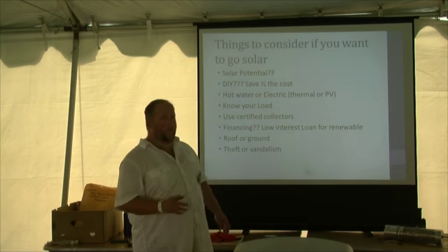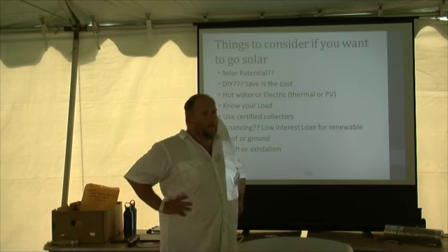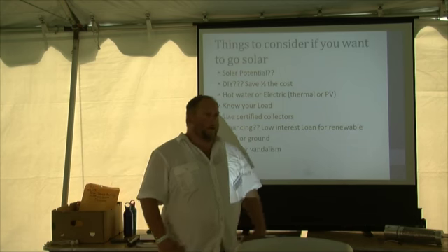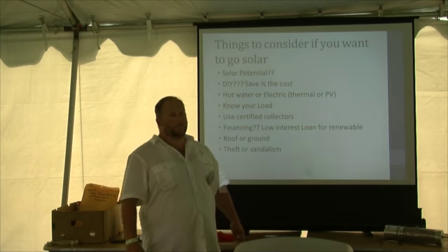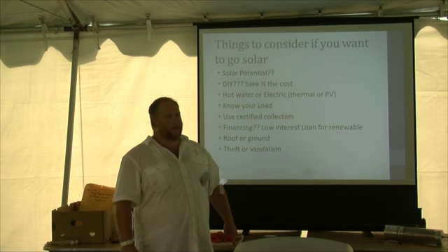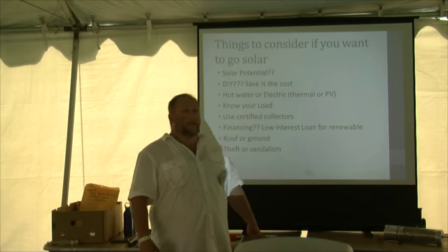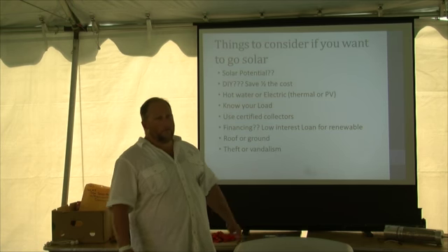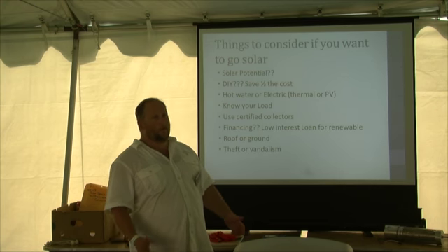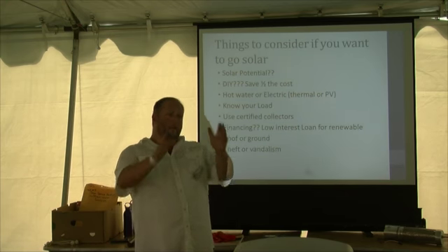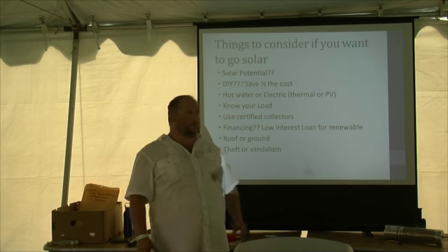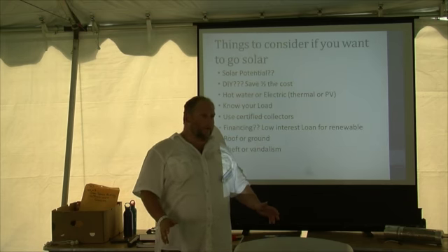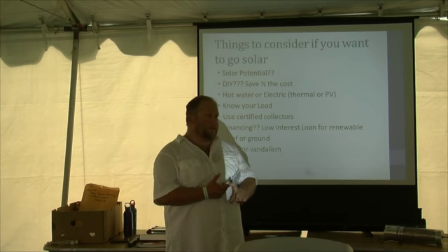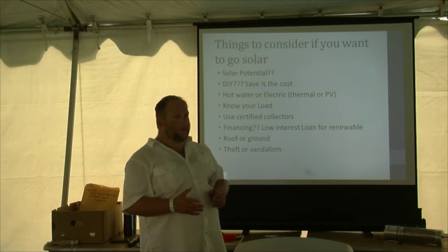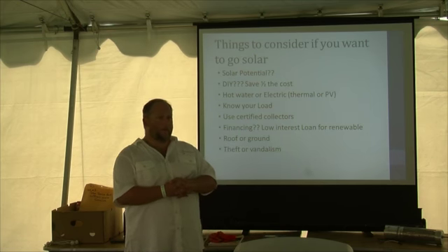So what do you think about the controversy between PVs and heat pumps versus solar thermal for hot water? I don't buy it at all — hands down, thermal is the way to go. Heat pumps are a great technology, but the payback isn't there, and there are more points of failure. Also, you have to fill your whole roof up with panels — if you see somebody with one or two panels on their roof, there might be just enough power for the refrigerator. With thermal, you get 70% efficiency versus 15%, so that's 10 square feet per person versus 50 square feet per person. You get 5 times the value.